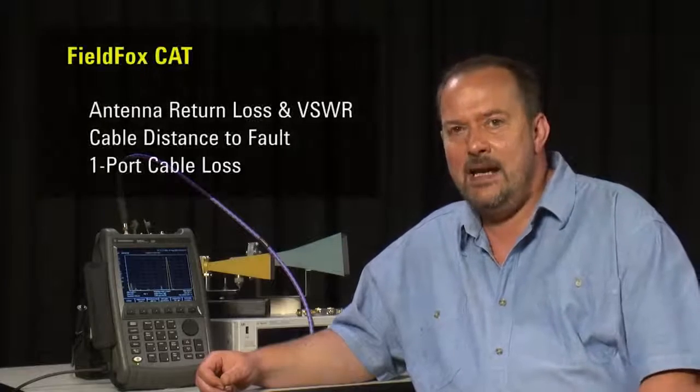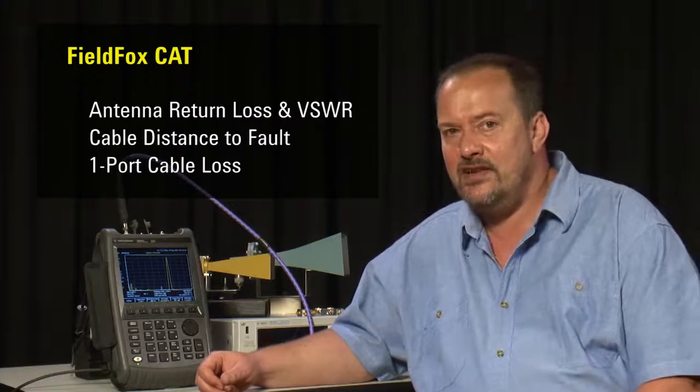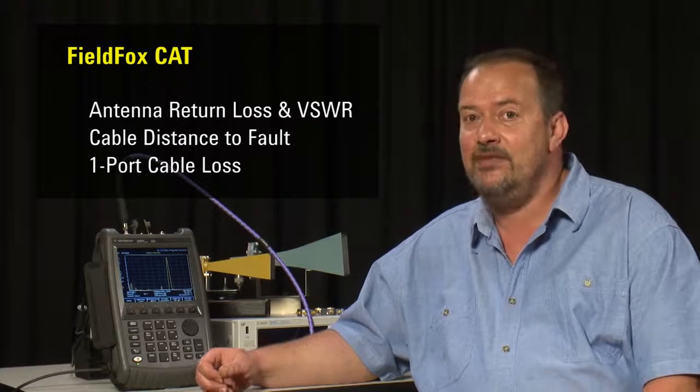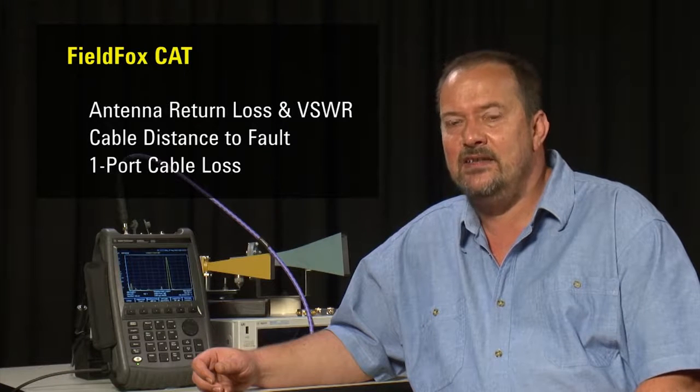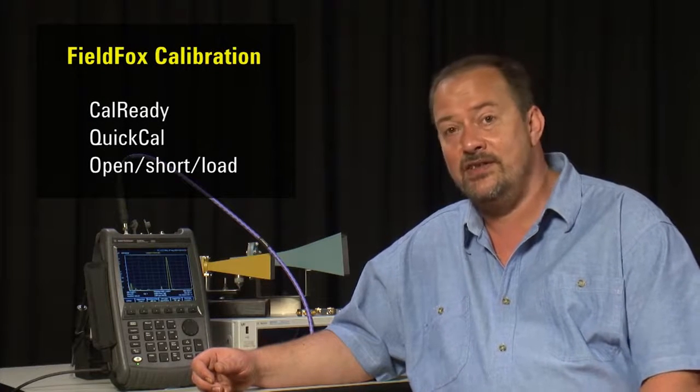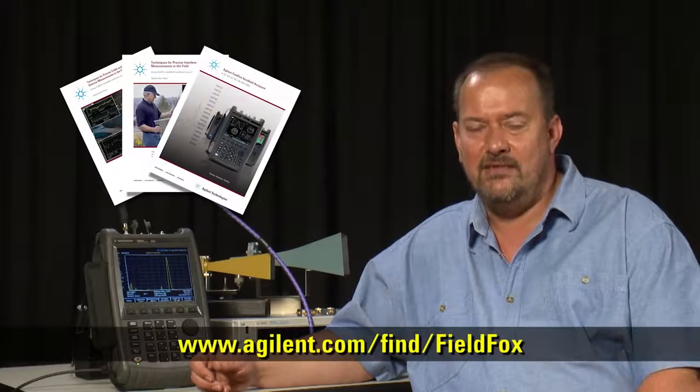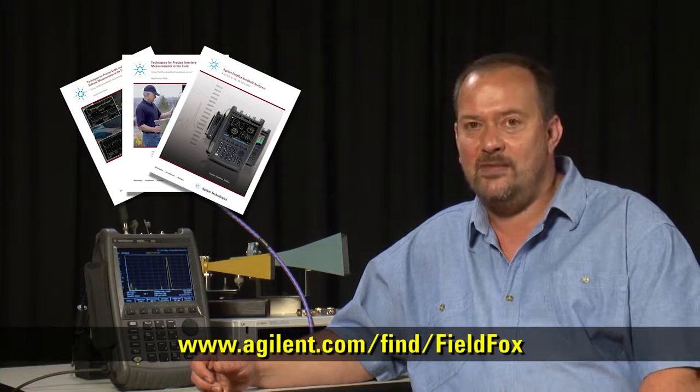In summary, we have been able to make return loss and VSWR measurements of antennas, distance to fault return loss and VSWR measurements of cables and antenna systems, and we can even measure the loss of cables just by connecting to one end of the cable. And at no time did we use a calibration kit. Of course, you can still use the traditional open short load calibrations that you are used to, but with the FieldFox, in many instances, you may not need to. For further information on the Agilent FieldFox Microwave Analyzer, please contact your local representative or visit the website shown below.